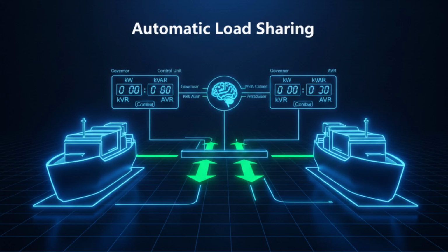Automatic load sharing. When multiple generators operate in parallel, load sharing is crucial. Unequal load distribution can cause reverse power flow, overheating, and premature generator wear. The PMS automatically adjusts each generator's active power, kW, using the governor and reactive power, kVAR, using the AVR, ensuring balanced operation. Load sharing also helps maintain stable bus voltage and frequency, even during sudden load fluctuations. Balanced loading prevents generator trips, blackouts, and ensures that essential machinery continues running smoothly.